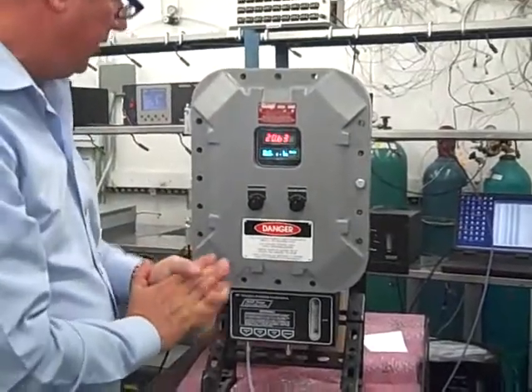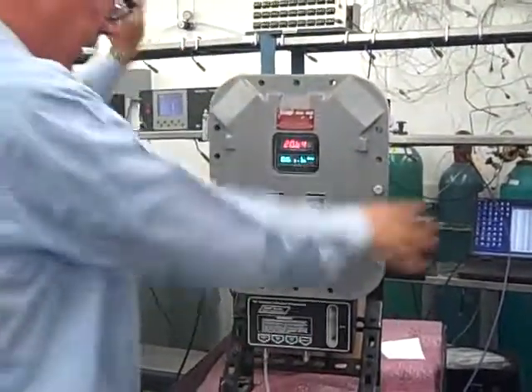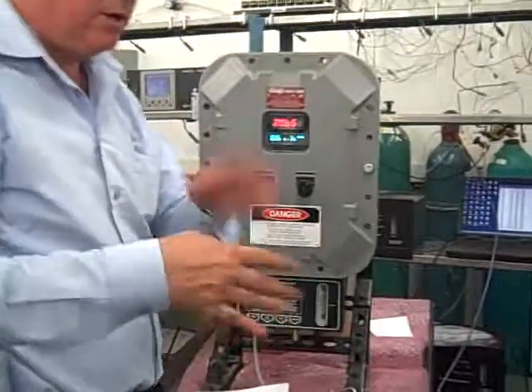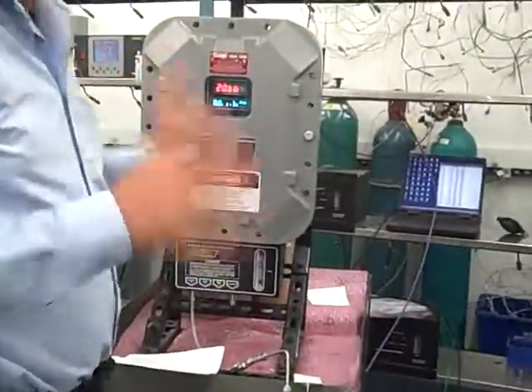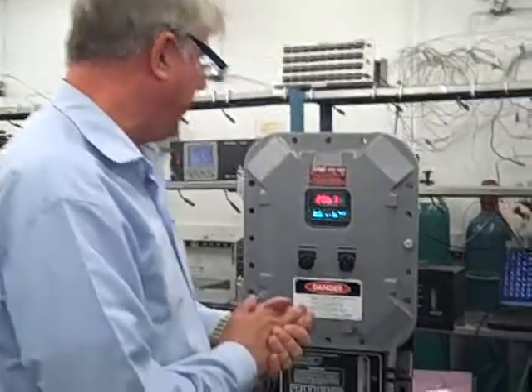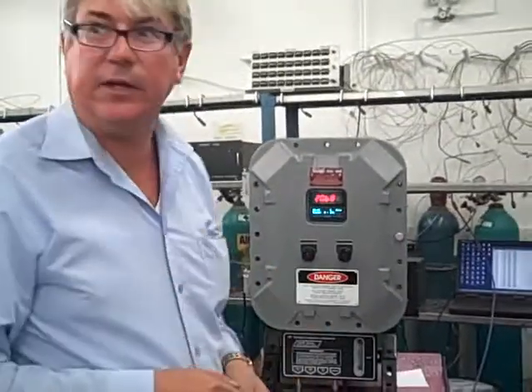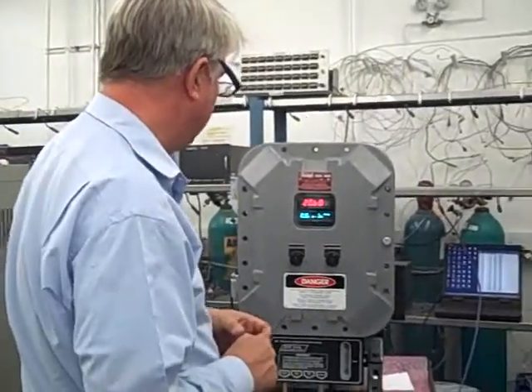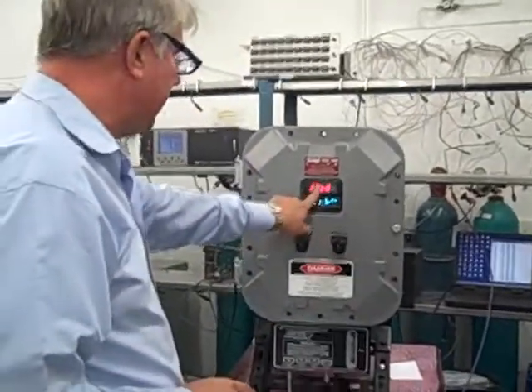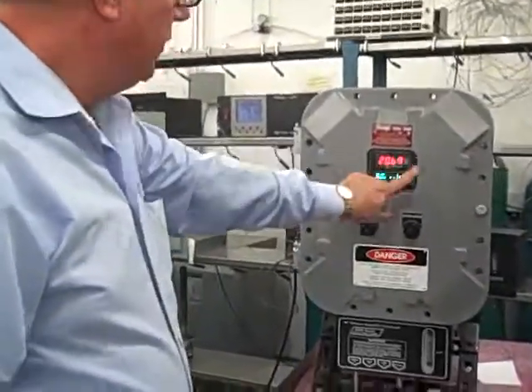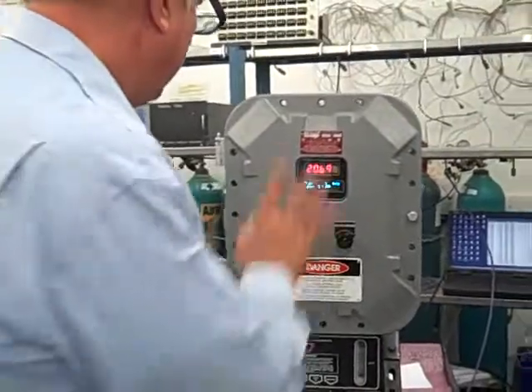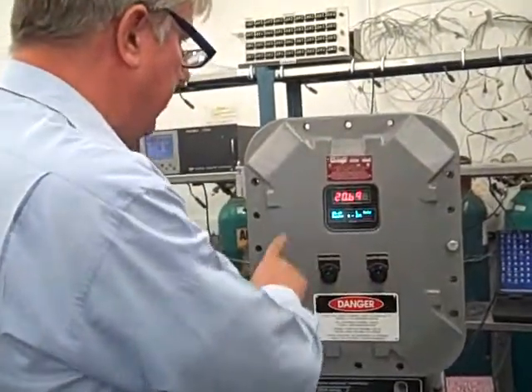so typically that's not a problem with the units, but it can happen if you're connecting tubing. Some customers want to connect plastic tubing to the unit. For a trace unit, we do not recommend that. You should use stainless steel tubing at all times, and good tight fittings, Swagelok or equivalent, those type of things. In any case, now we can see we are on the 25% range, and we're going to go ahead and show you how to operate the unit now.